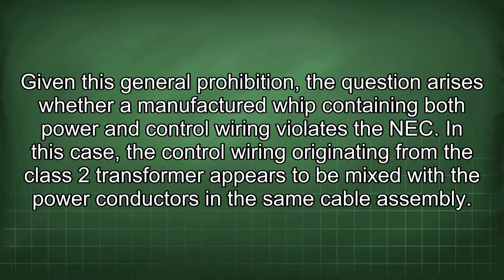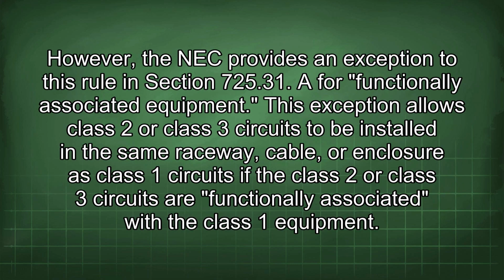Given this general prohibition, a question arises whether a manufactured whip containing both power and control wiring violates the NEC. In this case, the control wiring originating from the Class 2 transformer appears to be mixed with the power conductors in the same cable assembly. However, the NEC provides an exception to this rule in Section 725.31 for functionally associated equipment.